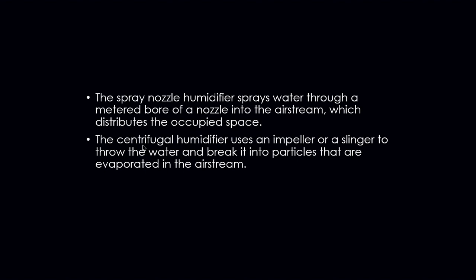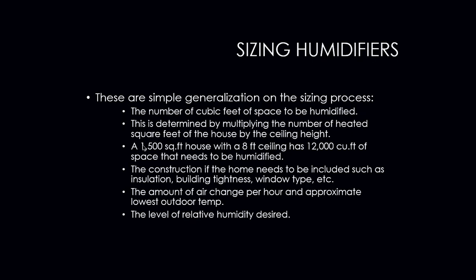The spray nozzle humidifier sprays water through a metered bore of a nozzle into the airstream, which distributes to the occupied space. The centrifugal humidifier uses an impeller or a slinger to throw the water and break it into particles that are evaporated into the airstream. Your pneumatic type humidifiers, atomizing systems, use air pressure to break up the water into a mist of tiny droplets and then disperse them. Okay, so there's a lot of different ways of doing this.